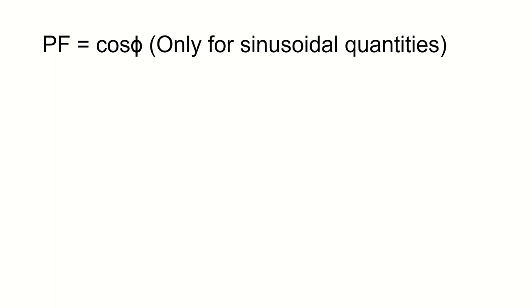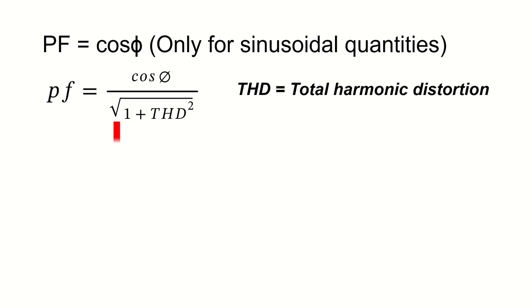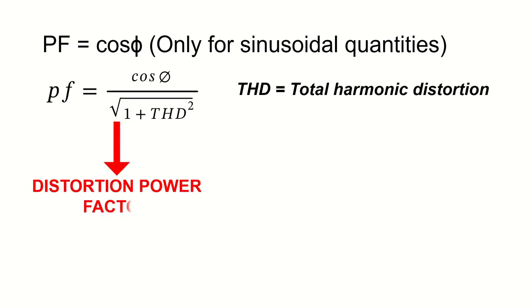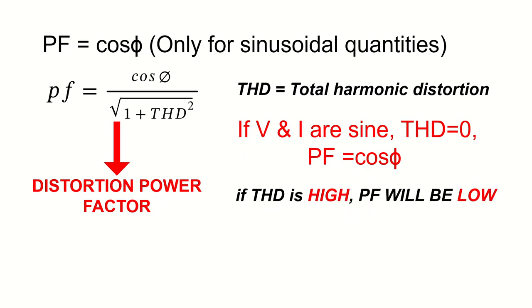Here the reason why we are getting a very low power factor is because of the distortion in the current. And the power factor is calculated using the equation, cos phi divided by root of 1 plus THD squared. Where THD is the total harmonic distortion. And this power factor is generally termed as distortion power factor. If both the voltage and current are sinusoidal signals, then THD becomes 0. And the power factor will be just the cosine of the angle between them. Since here THD is very high, we are getting very low power factor.